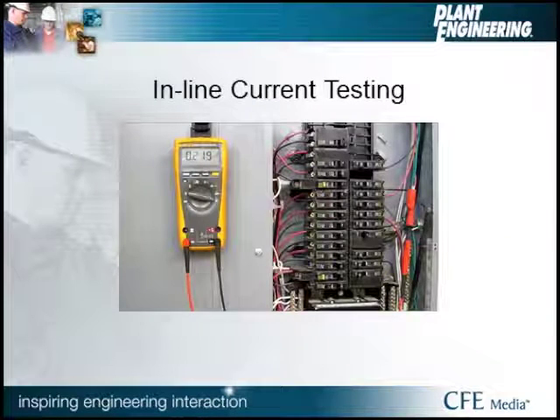Here we'll watch an inline current test performed. Now, before this is set up, we lock the equipment out, make sure that we do a test to make sure that it's been de-energized, then we put our inline leads in place.